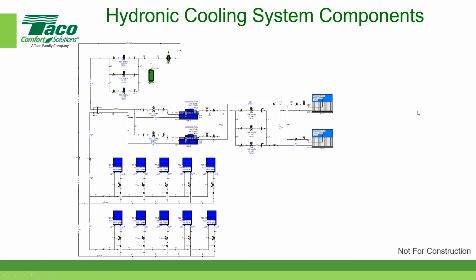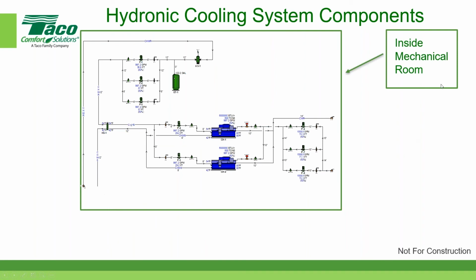If I use pumps, let's go to the next slide here. If I use pumps, whether I'm using condenser water or chilled water, in my secondary pumping system, I like to have three pumps, each sized for 50%, so that if I should lose one of these pumps, I have 100% capacity. And I always have a standby. So if all three pumps are available, and two are running, the third one would operate as standby. So both my chilled water and condenser water operate that way.